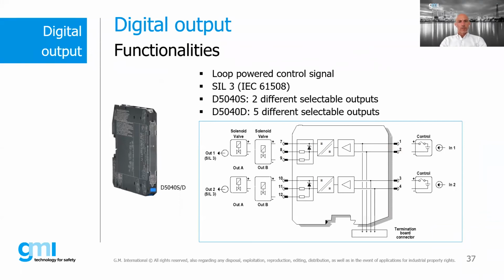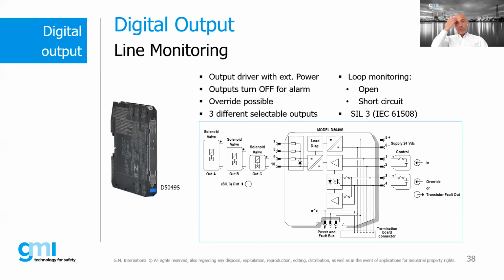Yeah. Thank you, Massimo. So let's go now with the digital outputs. We have a solution with the loop powered signal, control signal for SIL 3 applications, and for single and dual channel. In this case, there are different selectable outputs that may be used with different loads, because also for safety reasons, you maybe need more power. In this case, you can select different outputs. And we also have a solution with auxiliary power, which grants to the load more power than the one given from the system.